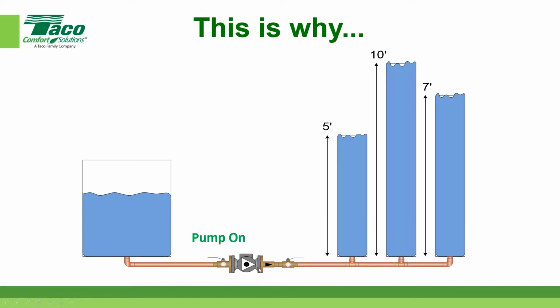Now, this is pretty intuitive at this point in time. If I have the ability to push up to 10 foot of head and spill water out this column, I'm also spilling water out of the 5 foot and the 7 foot as well. So I don't need to concern myself with any more head than the worst case. Hopefully that helps. A picture's worth 1,000 words, and you might have seen this before and just not got your arms around it. That's why I drew it up. I used to draw this on a blackboard, but it's just easier to show it this way. So hopefully that makes sense, and will help you understand why you only use the worst case of a parallel pipe system.